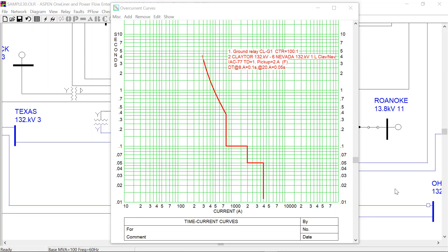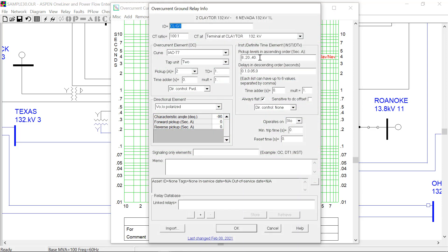In OneLiner version 15 overcurrent relay model, you can now enter the definite time element with up to 5 levels like this. Just enter the setting and the delay as a list separated by comma in those entry boxes.